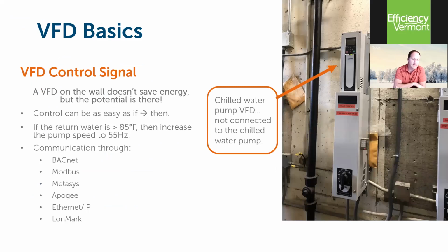Control signal: simply putting a VFD on the wall doesn't save energy. It's got to be installed correctly. It's got to be started up correctly. It's very similar to the programmable thermostat in your home, be that a 5-2 thermostat or a Wi-Fi thermostat. It's as good as the settings. And periodically, it's good to go back and check those settings. We at Efficiency Vermont will be talking internally about doing periodic recommissioning just to make sure that the drive settings are correct and that the intended savings is preserved.